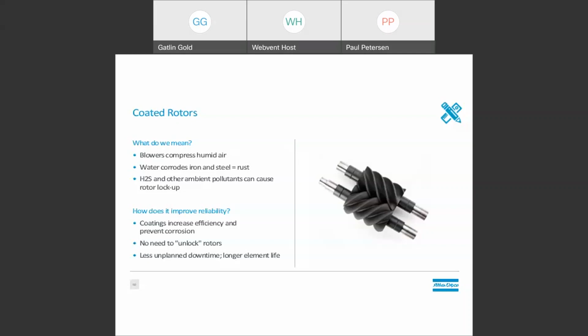After prolonged periods of downtime, uncoated rotors can lock up due to that rust formation. They can be broken loose with a long breaker bar, but at that point, that element's running on borrowed time. You should really order a replacement element once it locks up. It will keep going once unlocked, but it's not going to last for long. Other common contaminants like trace amounts of H2S or chlorine that are commonly found in wastewater treatment plants will accelerate the corrosion process. So coatings on the rotors not only prevent that corrosion and eliminate the chance of lockup, but they also provide better efficiency by reducing the gap between the rotors and casing. This gives you a higher efficiency and a wider turn down, resulting in lower energy cost. So in short, coated rotors prolong equipment life, prevent unplanned downtime, and increase your aeration system efficiency.